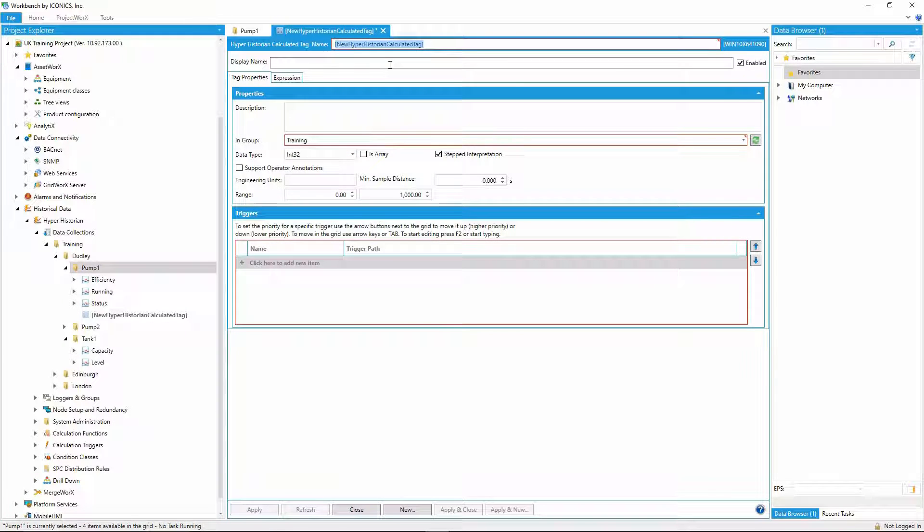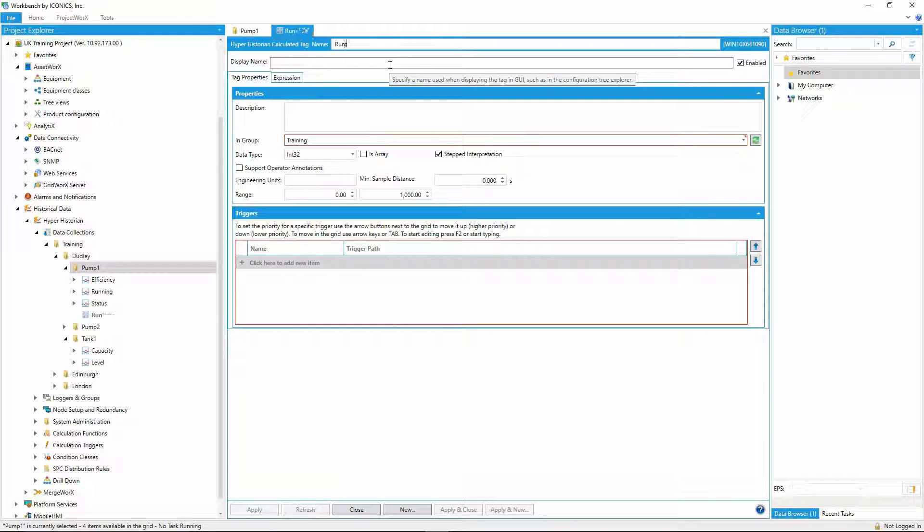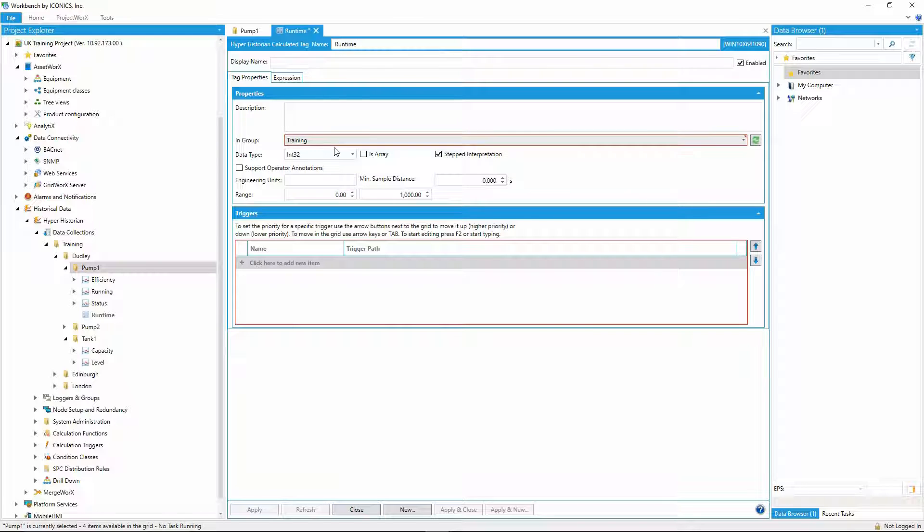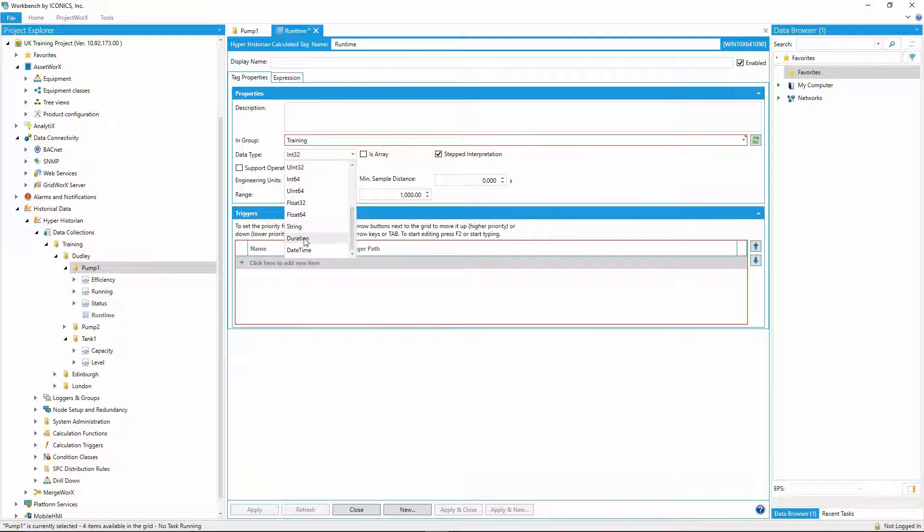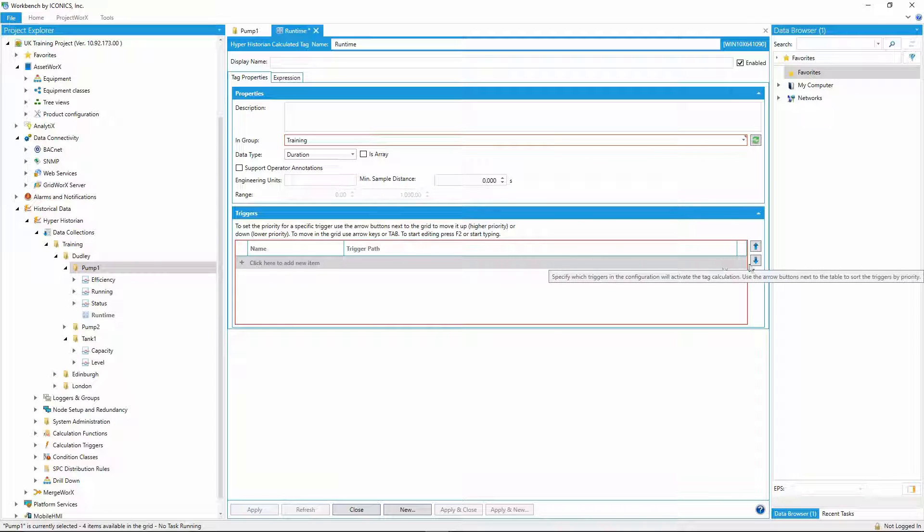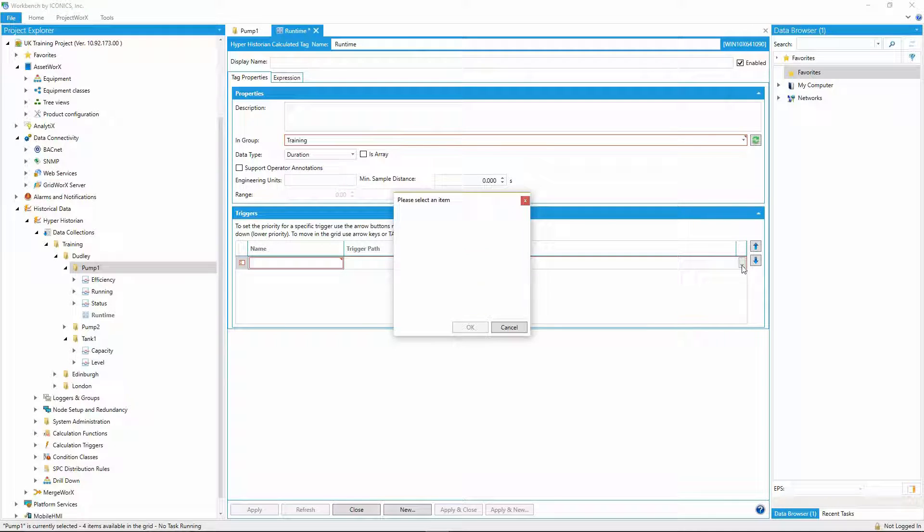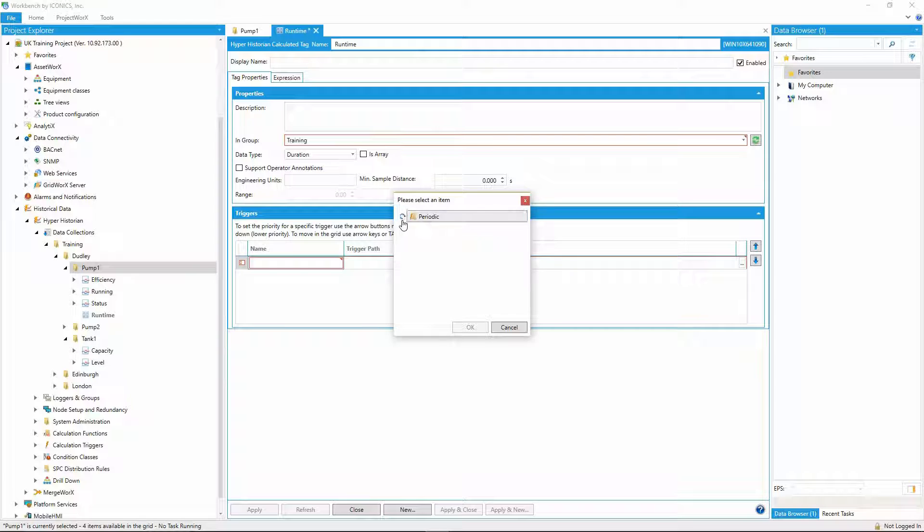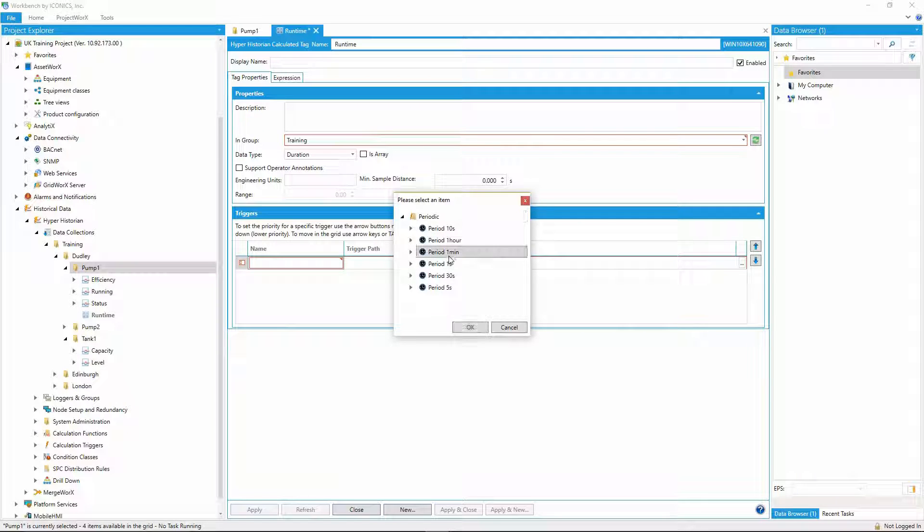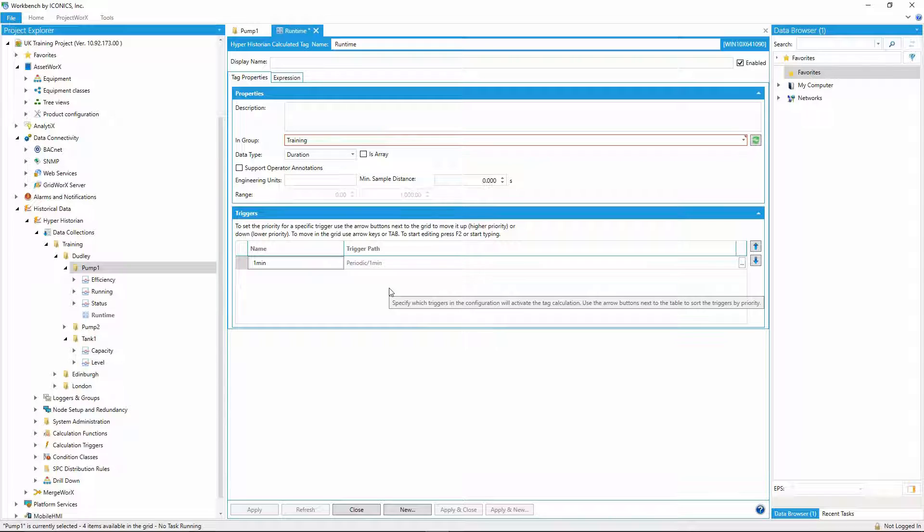I can add a new calculated tag to the asset and call it runtime. I'd like the output to be a time-based value, so I'll set the data type to be duration. And I'd like to evaluate this calculation every minute, so I'll set up a trigger to fire this calculation every one minute.